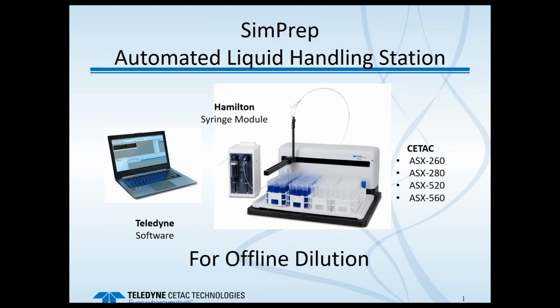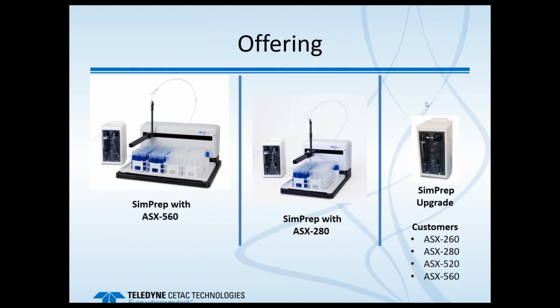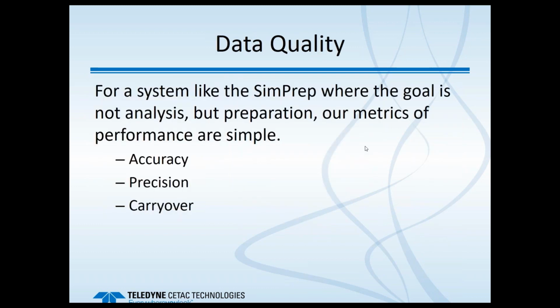So the system itself is comprised of essentially 3 components. There's the software, the Hamilton syringe module, and one of our CETAC auto samplers. The system can be run with the 560 or the 280, depending on space requirements within the lab. We also offer a SimPrep upgrade path for people who have an existing auto sampler that's not presently in use. They can use that to upgrade with the syringe module and the software, so that they can have a little bit more of a discounted way to get to the new product.